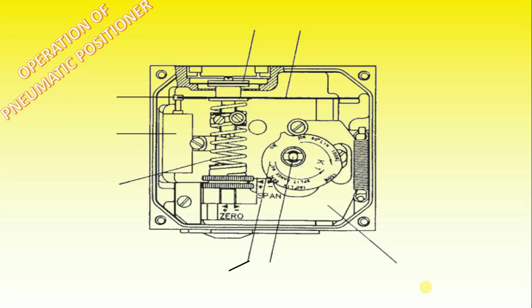The pneumatic positioner operates on a force balance principle. Assume an equilibrium position. An increased control pressure will deflect the diaphragm down, compressing the feedback spring.